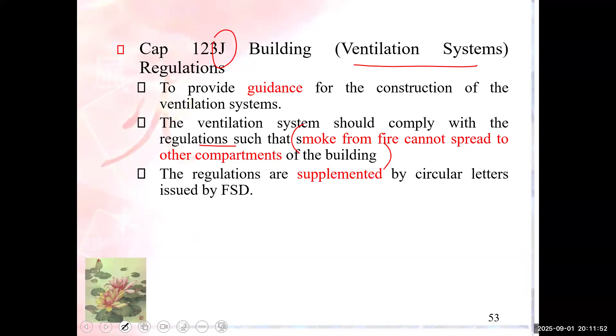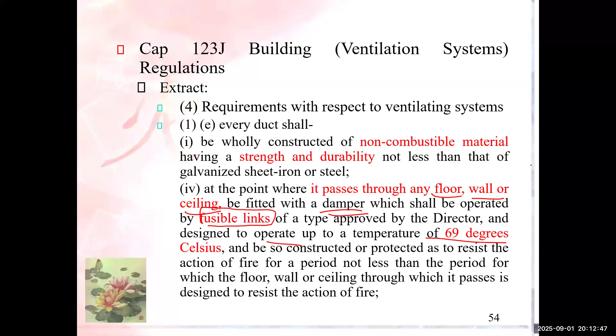For example, there may be dampers - smoke dampers or fire dampers with fusible links - which will cut off or prevent smoke from traveling from one location to another. Such dampers are usually installed at passages through partitions, walls, or vertically through floors, wall, or ceiling. They operate up to 69 degrees Celsius, similar to the red bulb sprinkler which is 68 degrees, but this refers to the dampers.